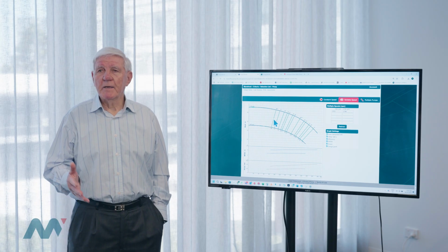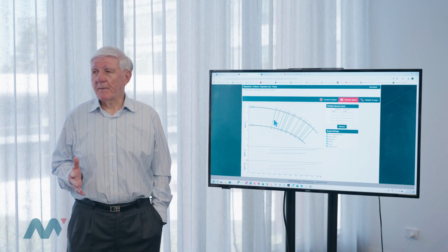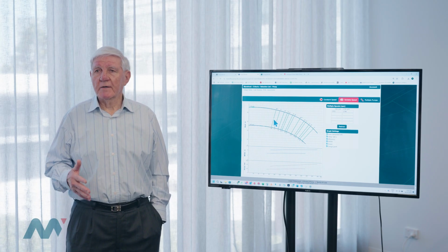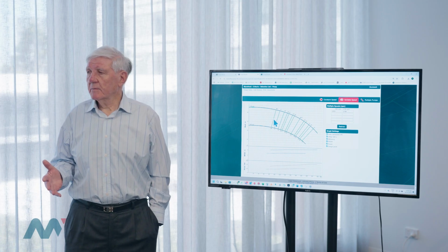So you'll get an immediate improvement in terms of pump output. But you will also get an increase in the kilowatt demand. You've got to take all of those things into account when you're looking at the bigger picture of how do you match the pump performance to the total system requirements at various load profiles.